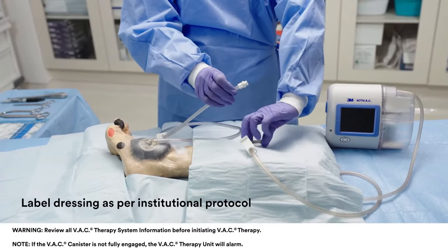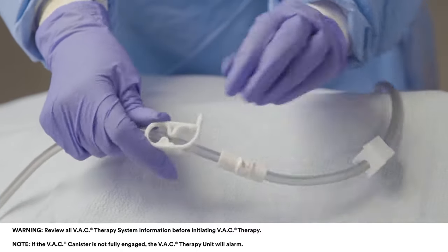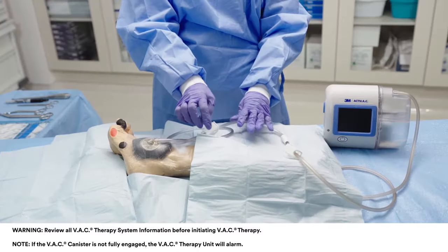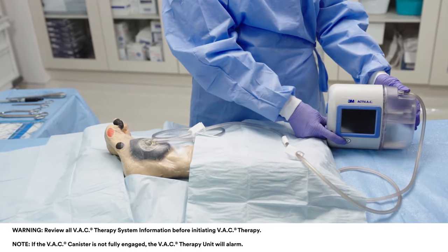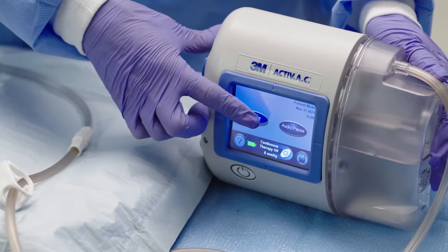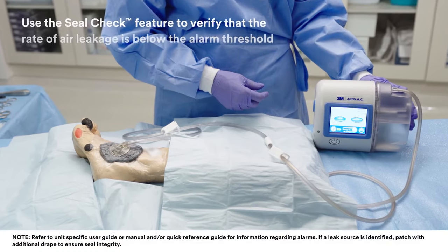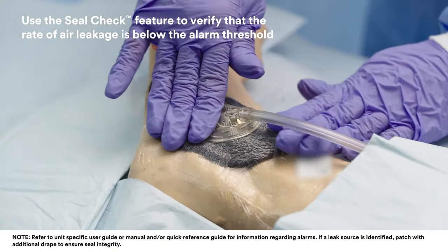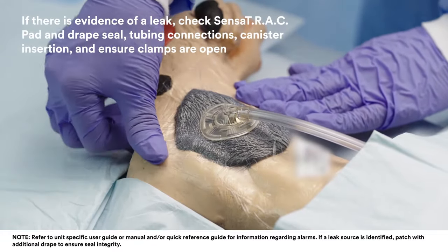Connect SensaT.R.A.C. pad tubing to canister tubing and ensure the clamp on each tube is open. Position clamps away from the patient. Turn on power to the VAC therapy unit and select the prescribed therapy setting. Assess the dressing to ensure seal integrity. The dressing should be collapsed and have a wrinkled appearance, and there should be no hissing sounds.